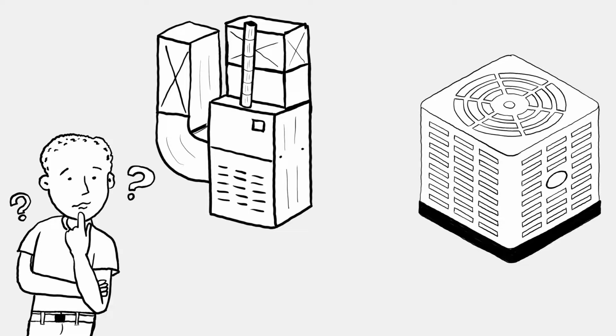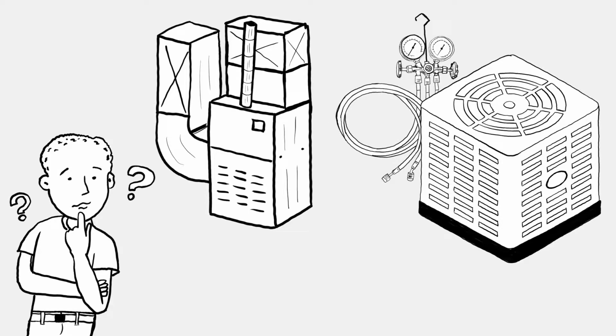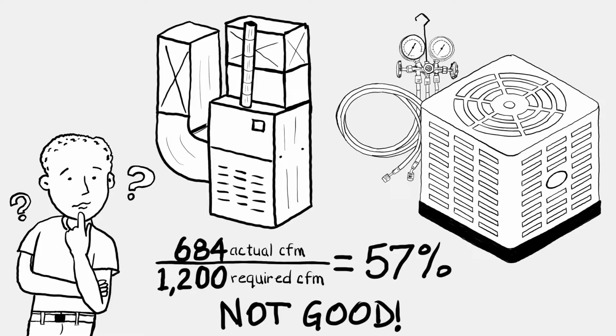Think about this. Can you properly set the refrigerant charge for a 3-ton system with only 684 cubic feet of air blowing across the evaporator coil per minute?